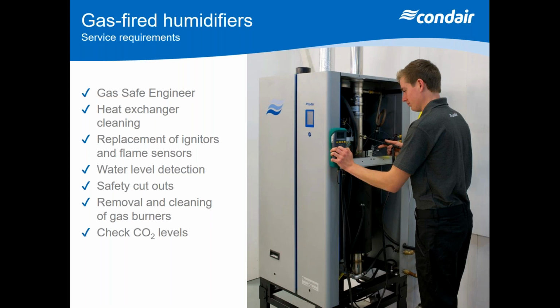Also, water level detection, as I said again, is a very, very important thing to consider. With the gas unit, as part of the main service, it's always recommended to check the safety devices, as in pressure switches on the airflows of the burner blowers. Also check the flue temperatures, making sure they're correct. And what we'd also recommend when you do a main service, when you're taking the burners out, is to do a complete check of the gas valve mixture to make sure you're getting the correct settings of that burner, so it's working as efficiently as possible.